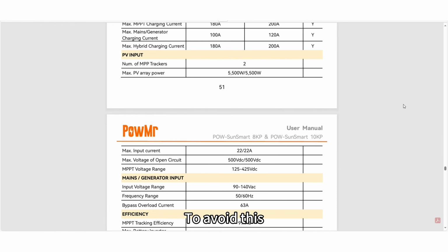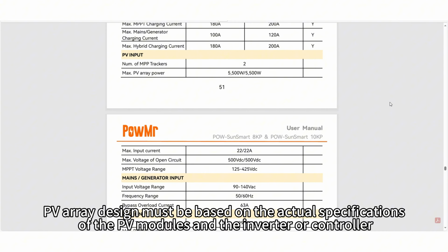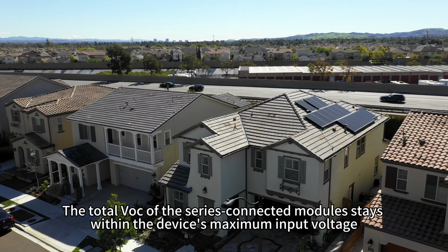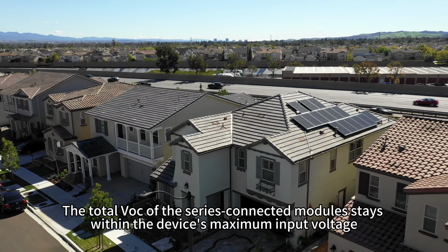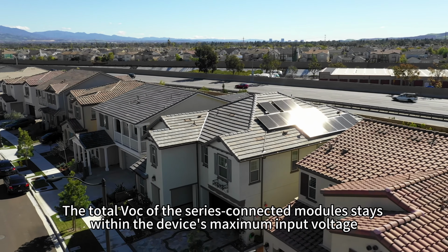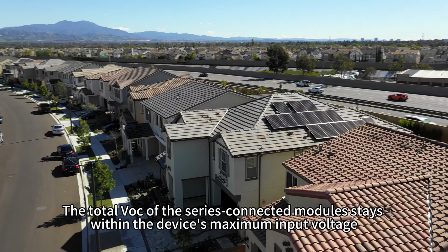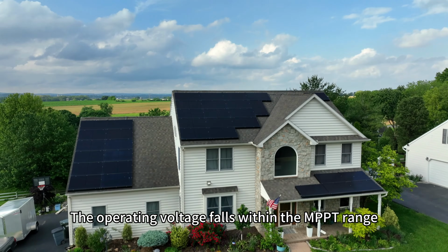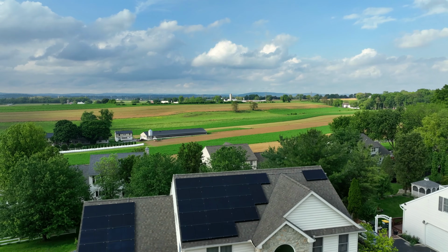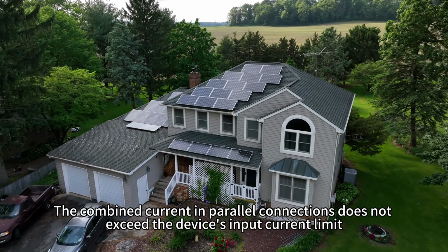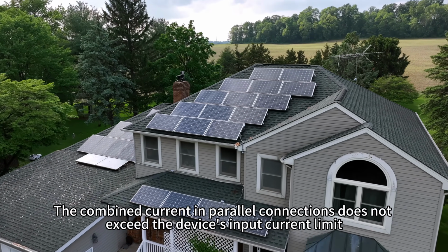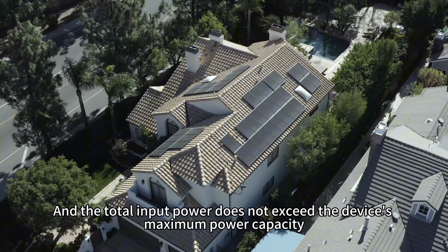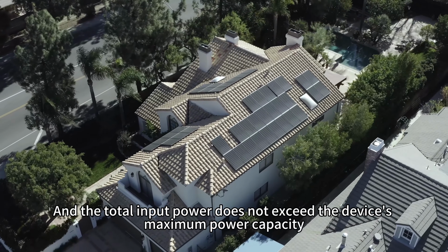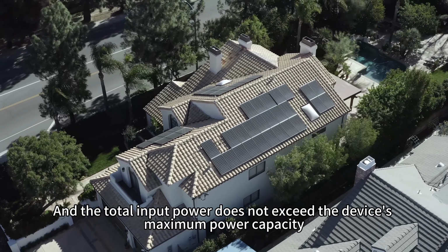To avoid this, PV array design must be based on the actual specifications of the PV modules and inverter or controller. Ensure that the total open circuit voltage of the series-connected modules stays within the device's maximum input voltage. The operating voltage falls within the MPPT range. The combined current in parallel connections does not exceed the device's input current limit, and the total input power does not exceed the device's maximum power capacity.